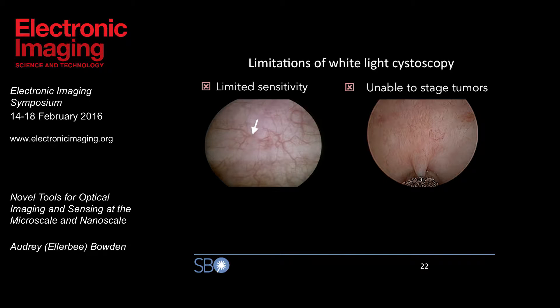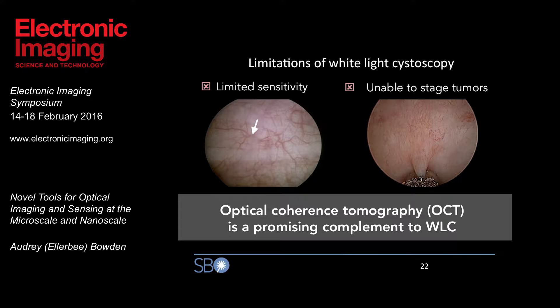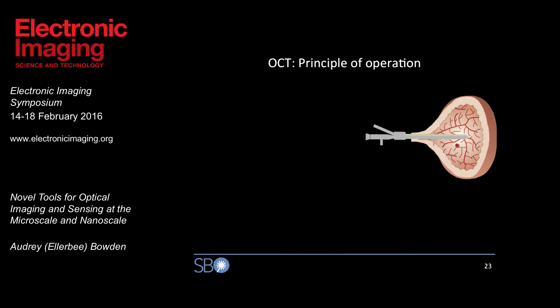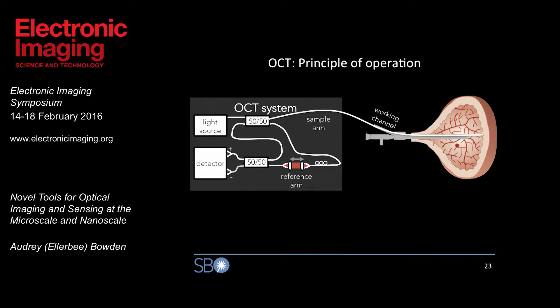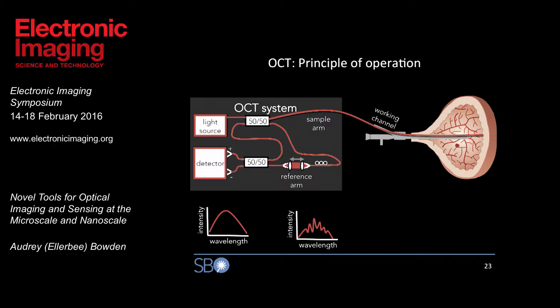OCT is a promising candidate as a complement to white-light cystoscopy, because OCT can see below the surface — which is very important in assessing not only whether a tumor is present, but also identifying its stage. The general principle of operation would be to create a probe that can be inserted into a standard cystoscope's working channel, connected to an OCT system, and then be able to look around the bladder and identify tumors even at the earliest stages. The light illuminates the system, gets sent to the sample, and we get back an interference pattern that tells us about the different layers of the bladder wall. We convert that into an A-scan and then into a cross-sectional B-scan.